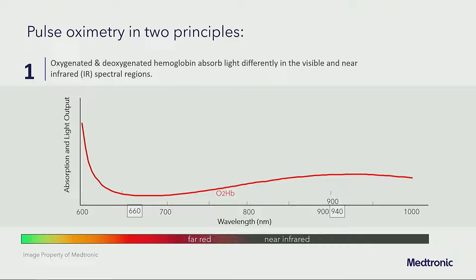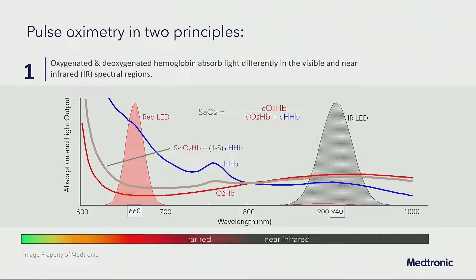So again, oxygenated and deoxygenated hemoglobin absorb light differently in the visible and the near infrared regions. So this is the absorption curve for oxyhemoglobin. You'll see its absorption is higher in the near infrared. This is deoxyhemoglobin. Its absorption is higher in red. And so this is our SAT. Two different curves that we're taking advantage of, and if you have any exams coming up, it may ask you, it's really kind of cruel to ask you for the numbers, but these are the numbers at 660 and 940.